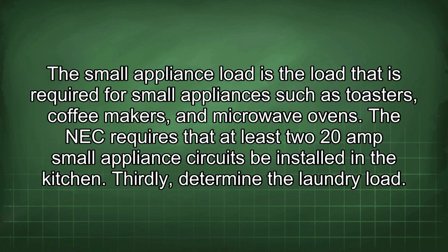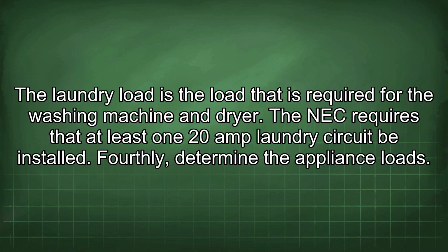Thirdly, determine the laundry load. The laundry load is the load that is required for the washing machine and dryer. The NEC requires that at least one 20-amp laundry circuit be installed.